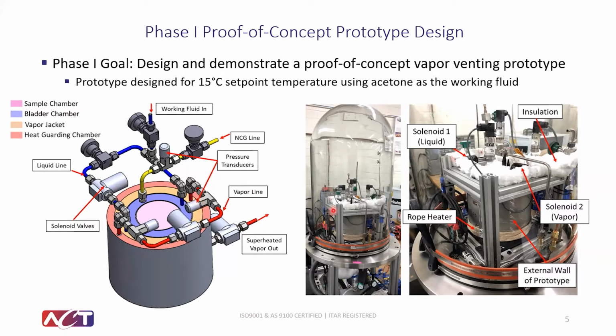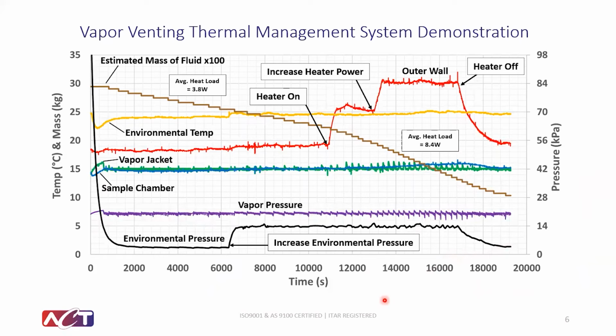On the right, we see the prototype placed within a bell jar. This was done so that the system could vent the low vapor pressure of acetone into an environment that was at a lower pressure. Heat loads were provided by a constant heat load from the ambient being warmer than the set point temperature. And then we also added an additional heater to the prototype so that we could increase the heat load. Here we see some experimental results.